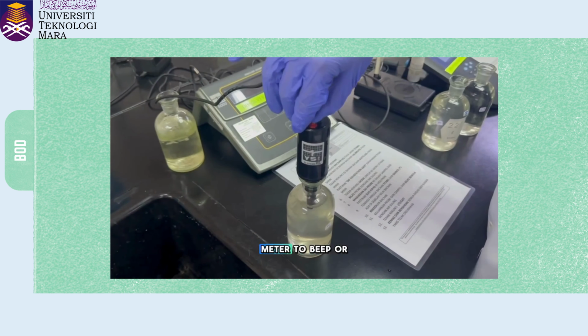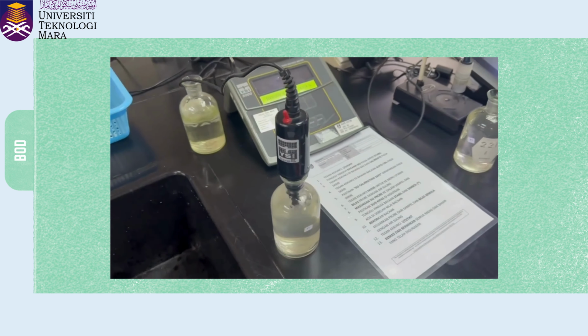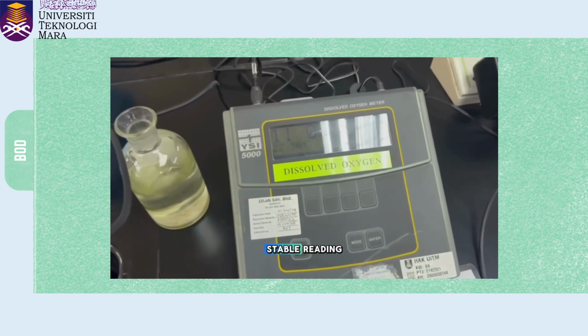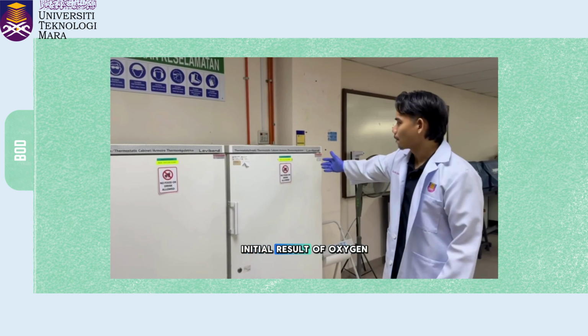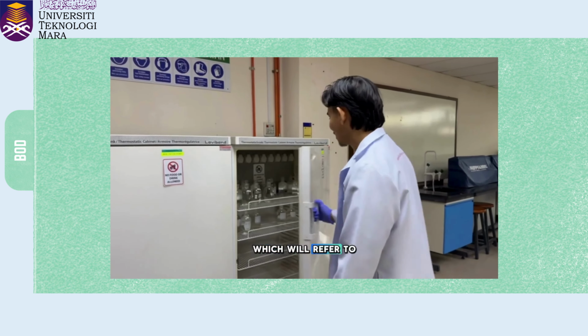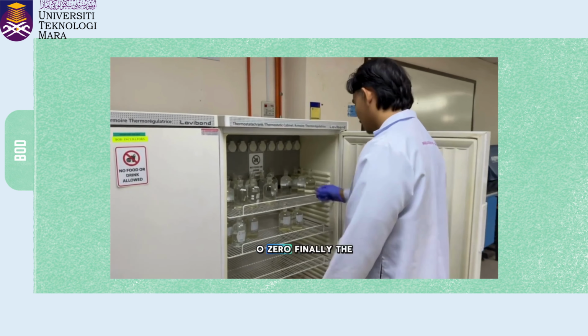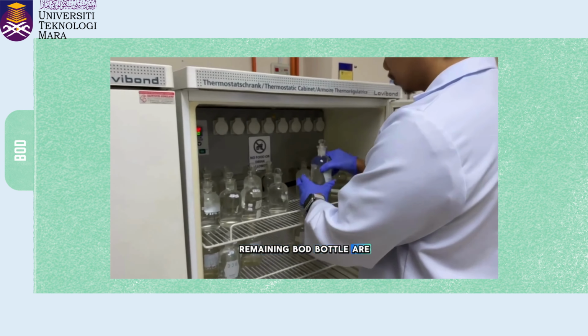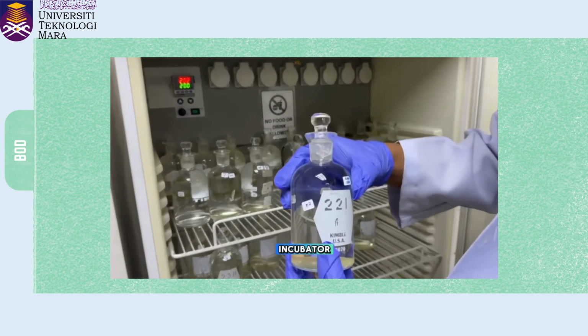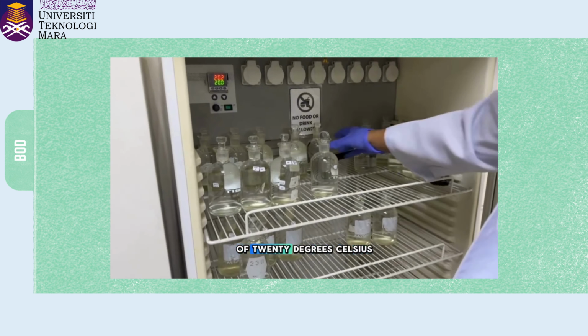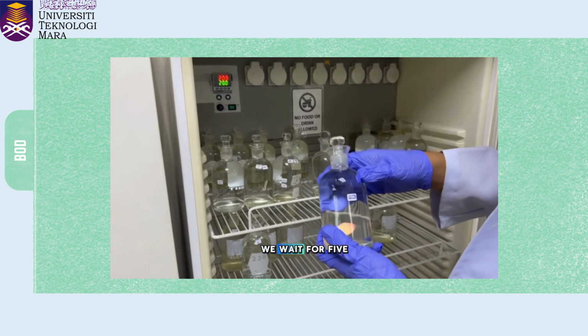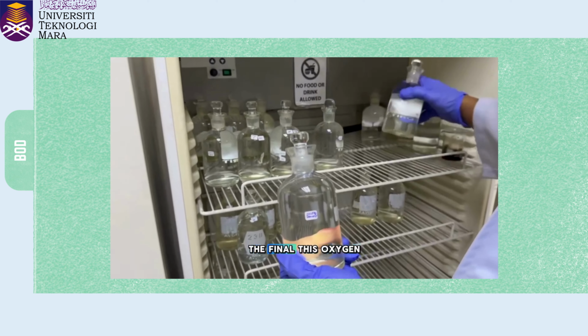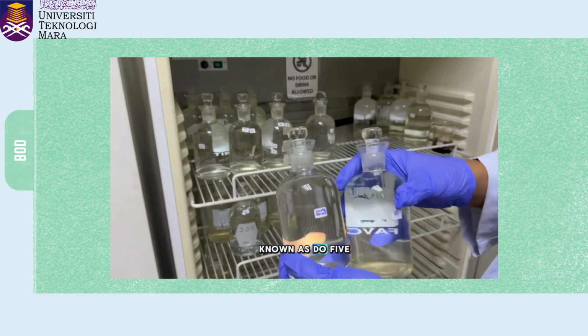We wait for the DO meter to beep or display the asterisk symbol. This indicates a stable reading, and we record the initial dissolved oxygen value, which we refer to as DO0. Finally, the remaining BOD bottles are stored in a refrigerator or incubator at a controlled temperature of 20 degrees Celsius. We wait for 5 days, after which we measure the final dissolved oxygen level, known as DO5.